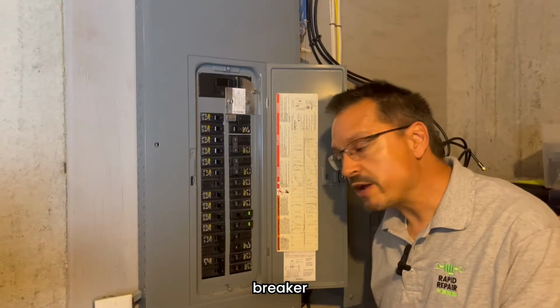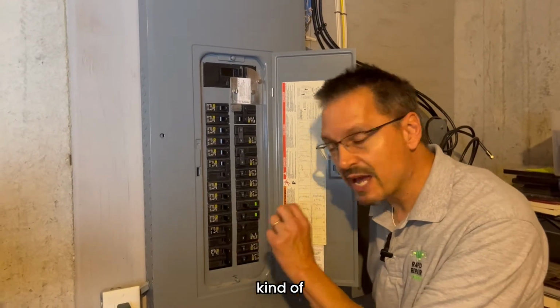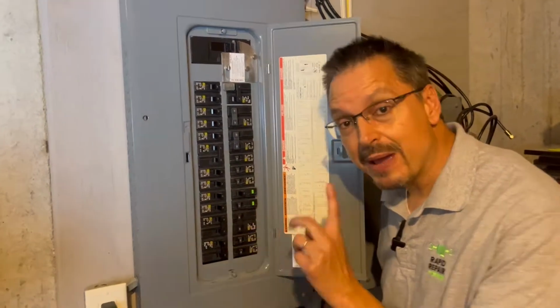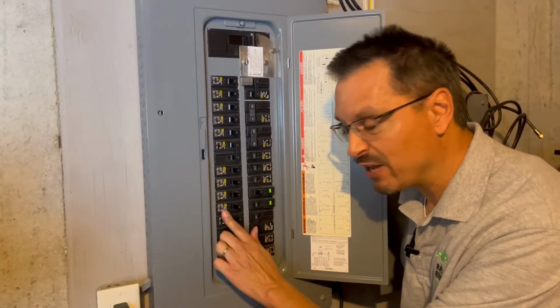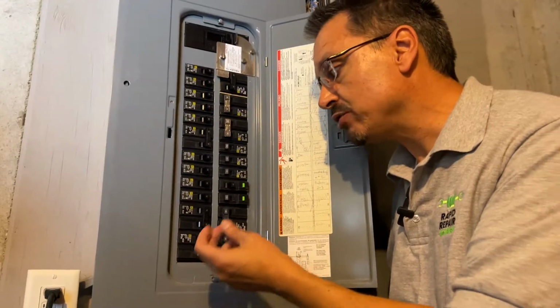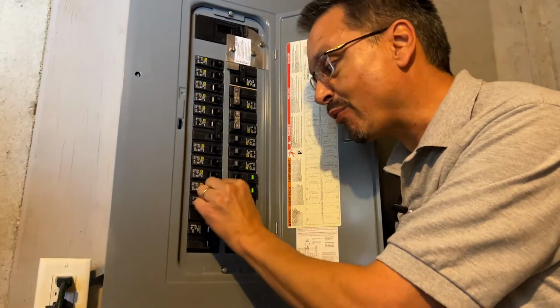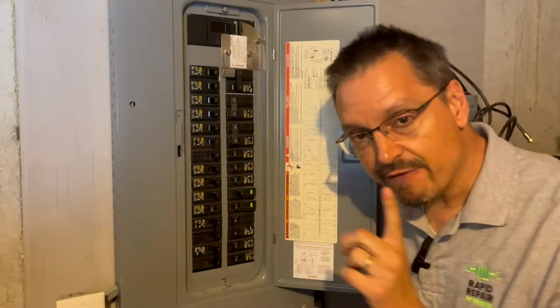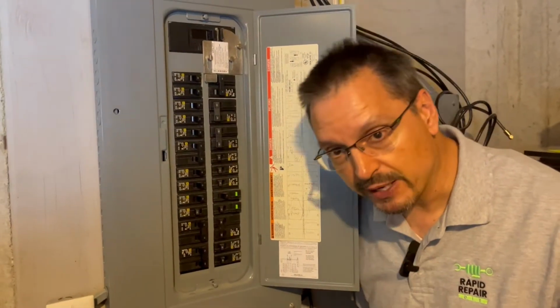Do you have a circuit breaker that is making a humming or some kind of a high-pitched sound? Maybe you have a circuit breaker that feels hot or overheating to the touch. Sometimes they actually get damaged. I've seen the little levers break off. I've seen cracks in them. If you have a damaged breaker or you suspect you have a damaged breaker, let's replace it.